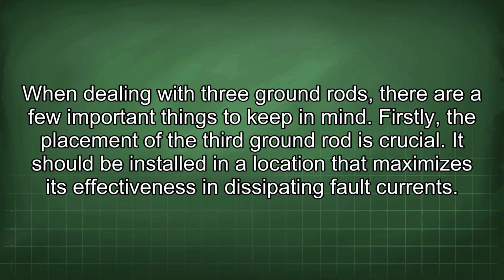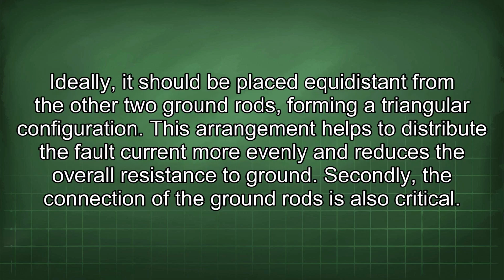When dealing with 3 ground rods, there are a few important things to keep in mind. Firstly, the placement of the 3rd ground rod is crucial. It should be installed in a location that maximizes its effectiveness in dissipating fault currents. Ideally, it should be placed equidistant from the other 2 ground rods, forming a triangular configuration. This arrangement helps to distribute the fault current more evenly and reduces the overall resistance to ground.